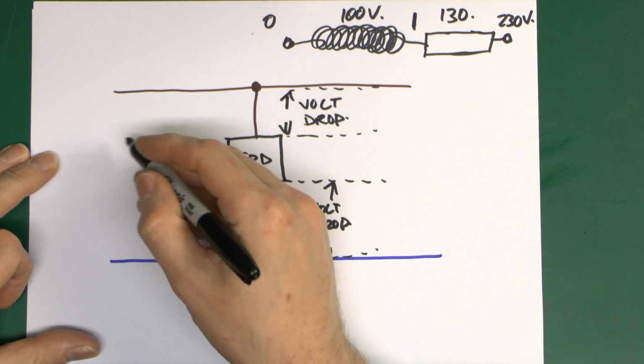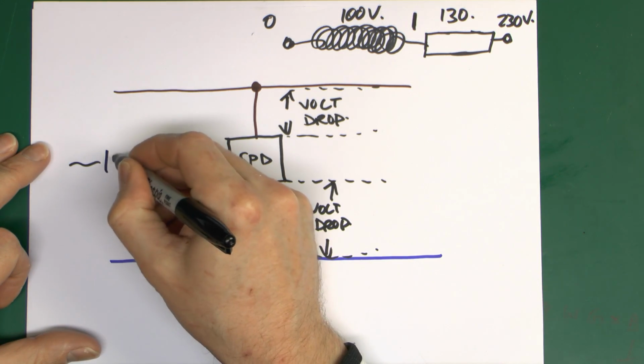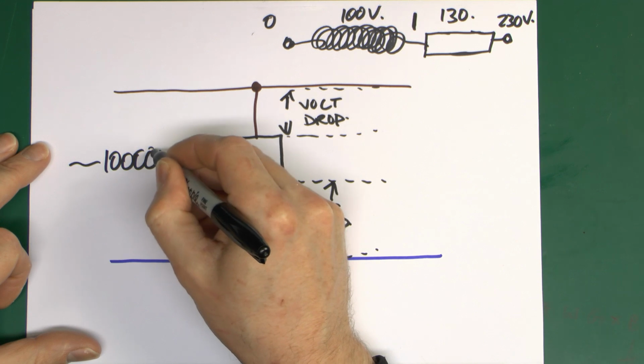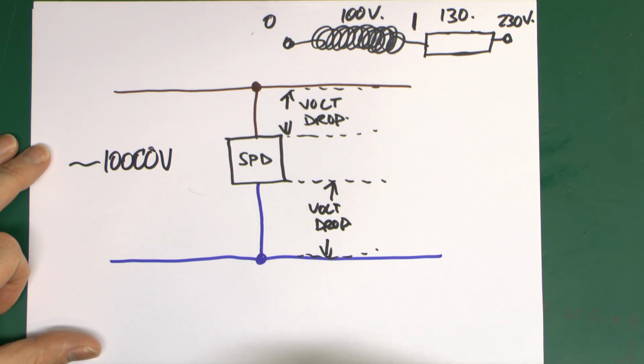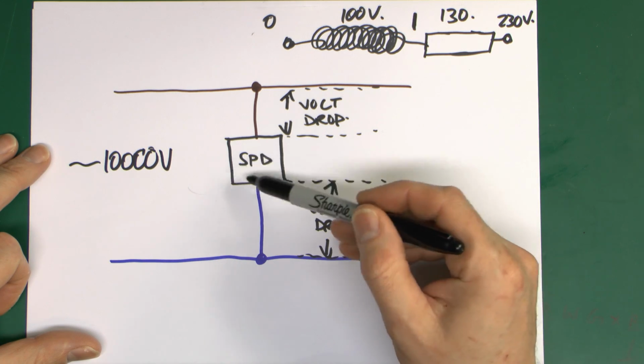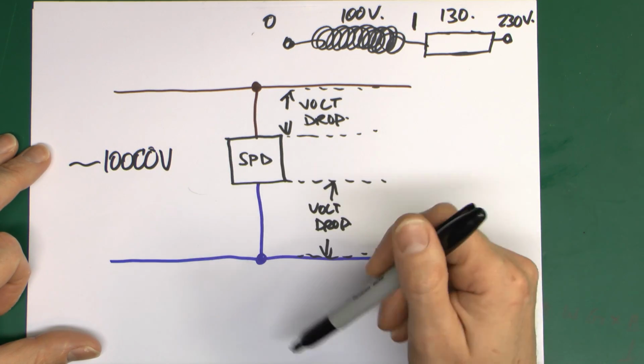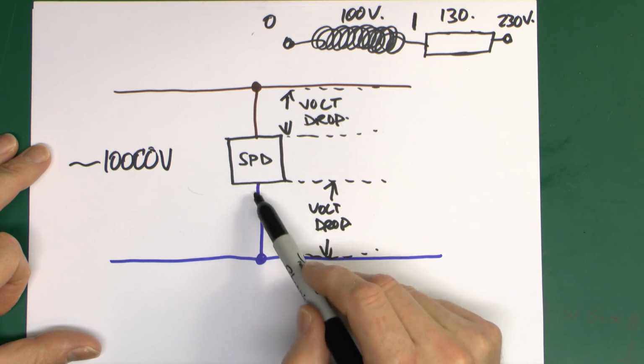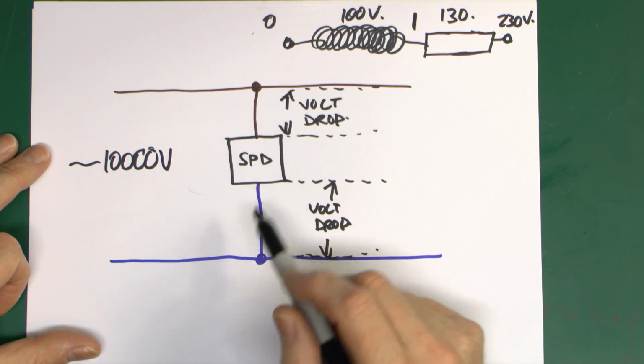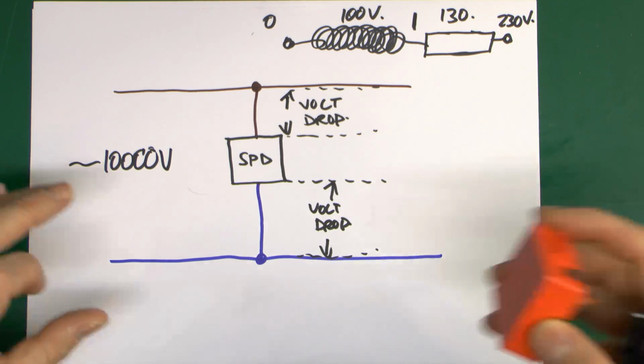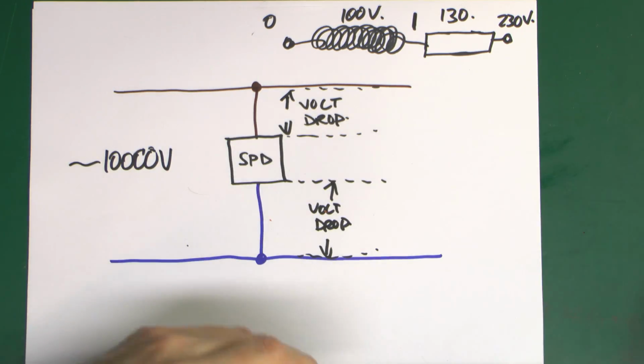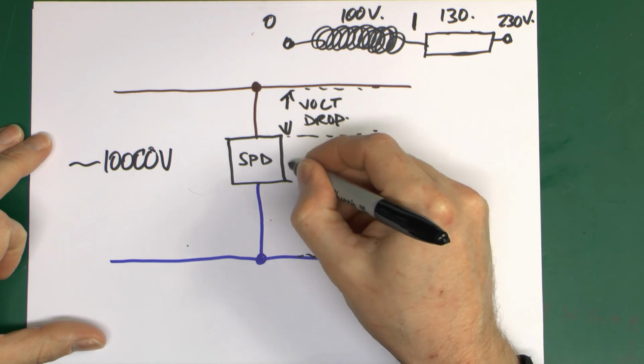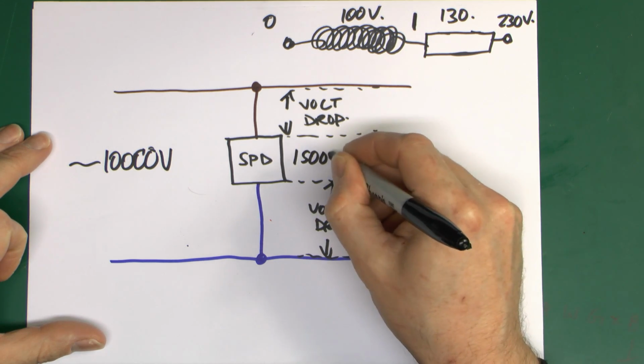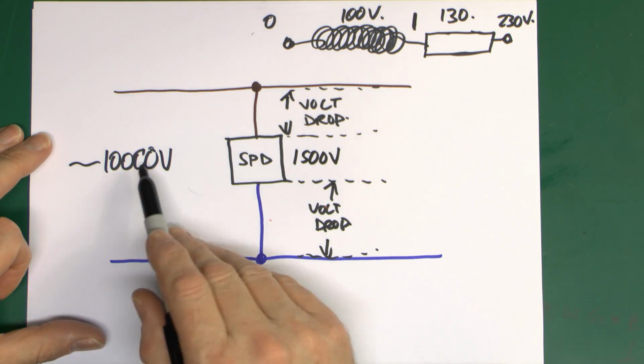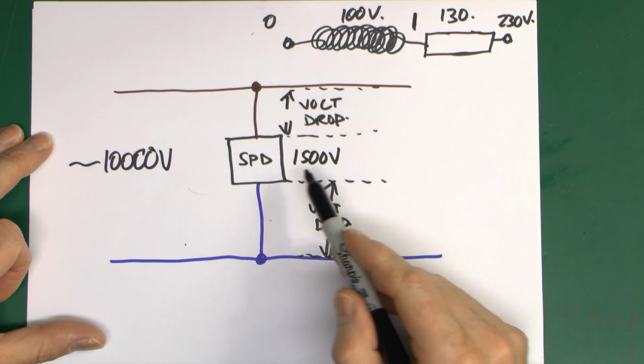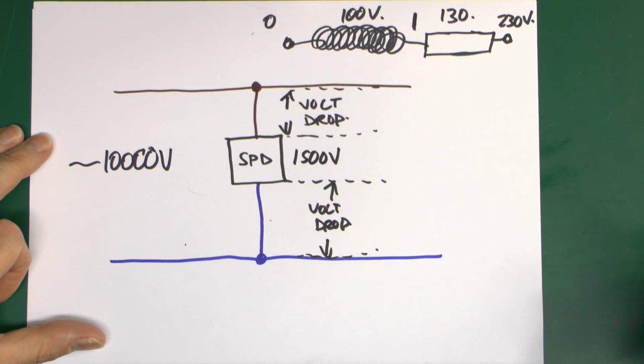So what might happen if you had a surge coming in here, say 10,000 volts from some sort of nearby lightning strike, is that the surge protection device will essentially conduct when that huge voltage appears, and then the voltage across the surge protection device will be considerably smaller, and this is actually printed on the front of the devices. So in the case of these orange ones, it's 1.5 kilovolts, so let's put that in there. So you get 1500 volts across the surge protection device, so the bulk of the 10,000 is removed, and you only get 1500 going across the equipment in the installation.